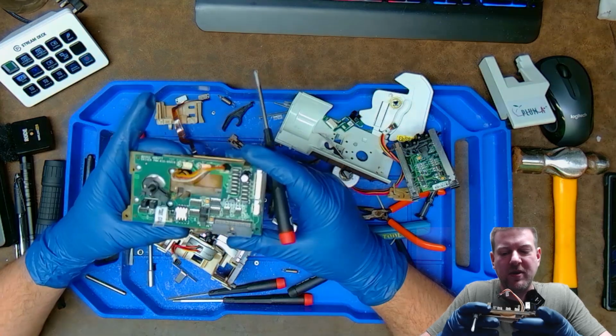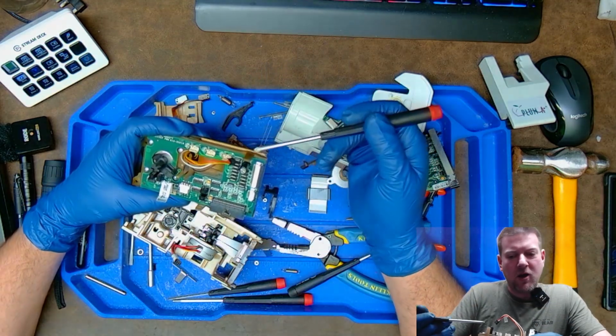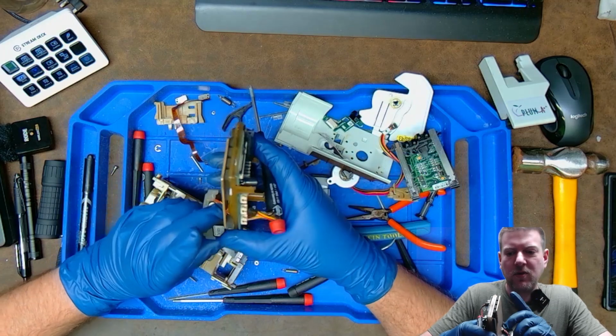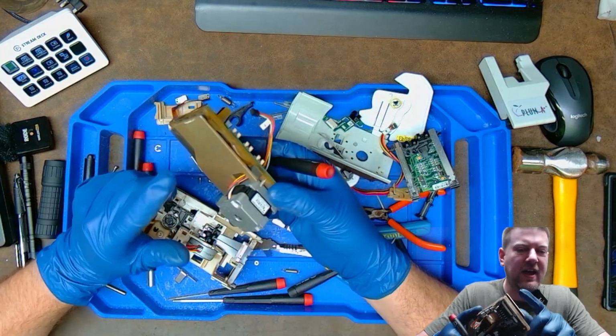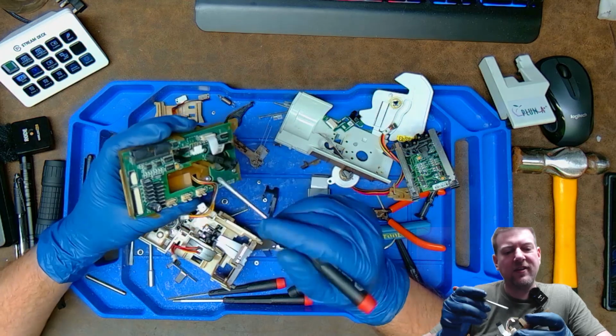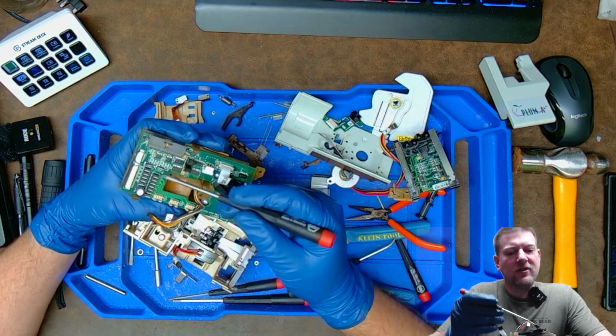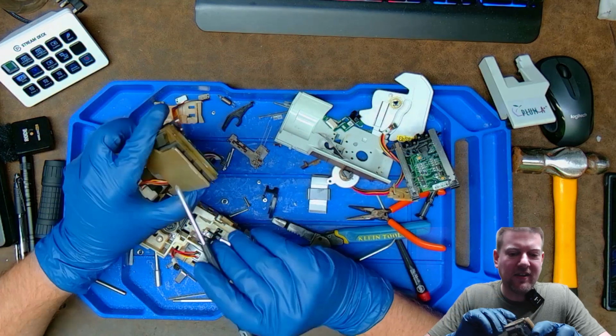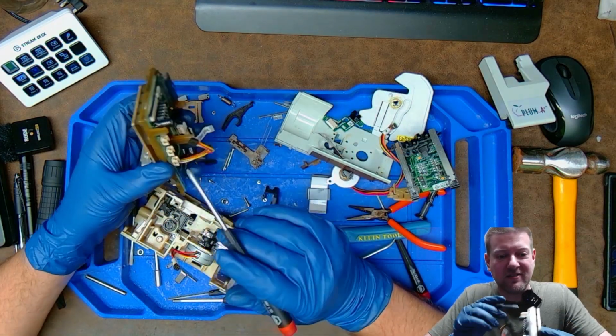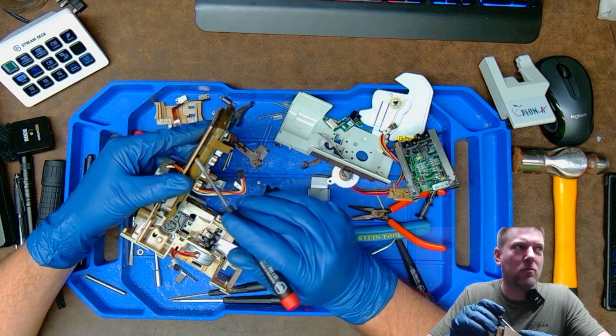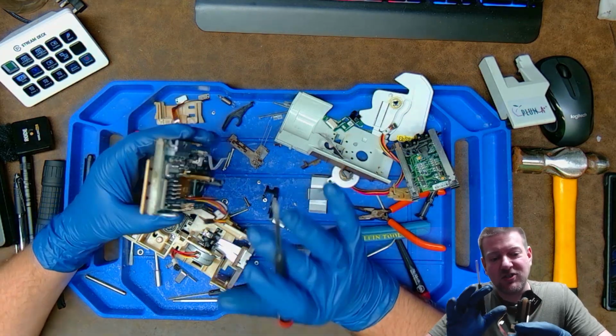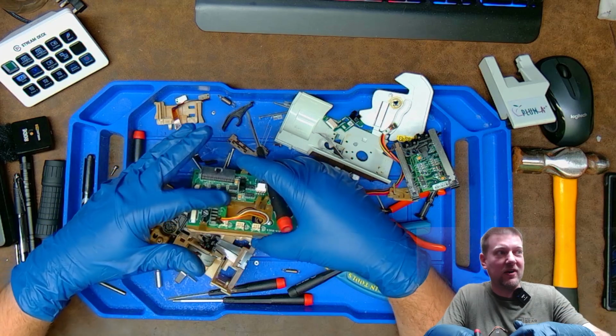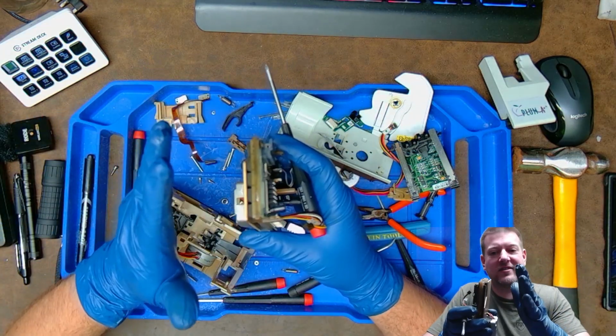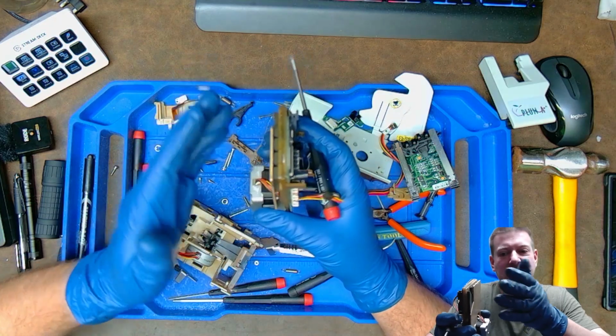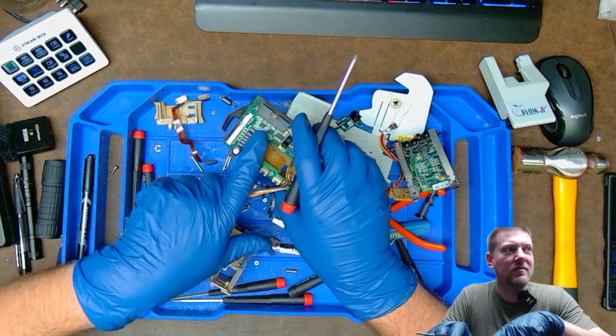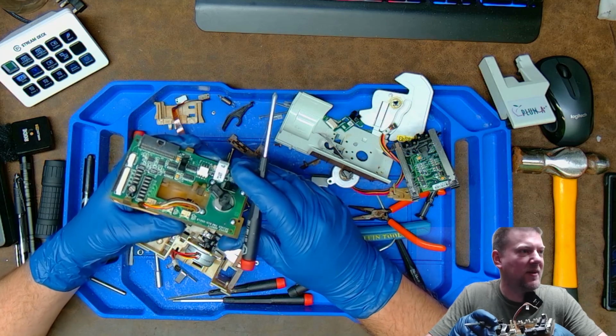All right, don't shoot the messenger, folks. Right here are your 3 motor outputs. And let's see, what else is going on with this bad boy? It's got this very heavy shield on it. And I think that's because these drivers are very noisy. So I think that is not a heat shield by any means. You can see it's offset and it's held by double-sided foam. I think it's a noise suppression shield that's suppressing these guys, which are buried in the middle of the pump, from any of the electronics, because you don't want any other inductors or any other components to be influenced by these guys right here. That's absolutely amazing.